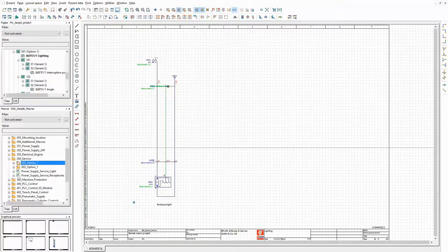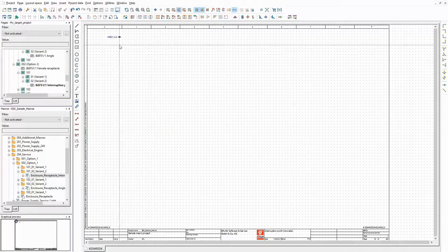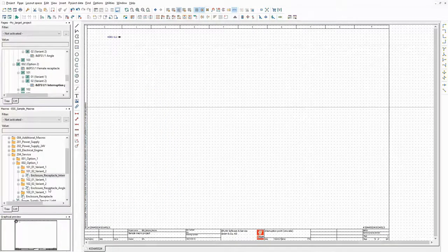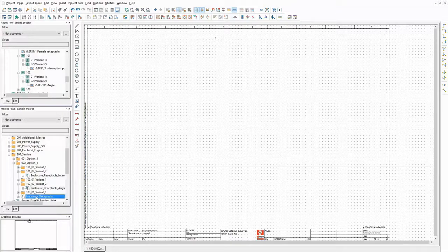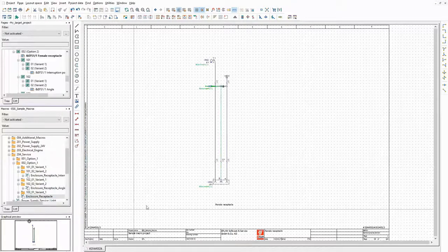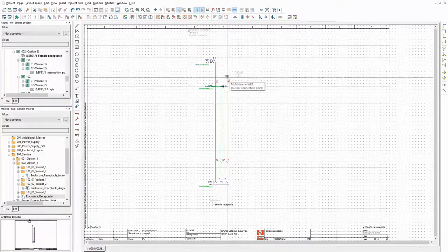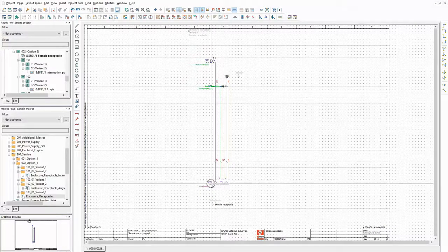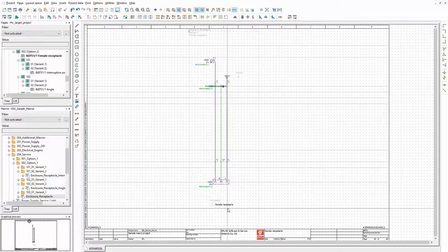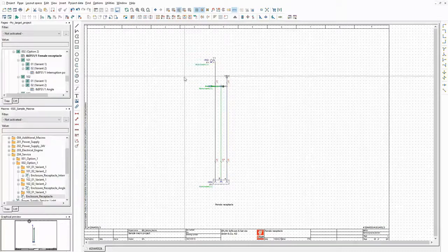I will use the following macros for a receptacle in the enclosure. They are structured similarly. This macro contains another interruption point. Then there is the single angle to redirect the connection. And this one is the receptacle. Again, there are two placeholder objects. I will use them in the same way as for the lighting. The first one is connected to the connection point of the bus bar. The second one is connected to the device tags of the receptacle itself and the circuit breaker. In addition, it will be possible to enter a free path function text.